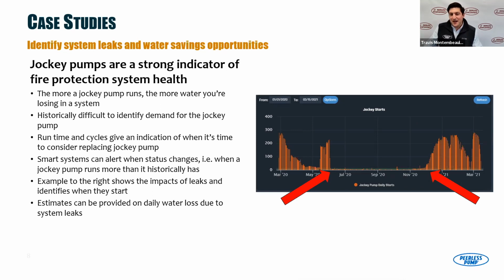So this site had 200, 300 starts per day. They tightened their system up in June of 2020, and they went down to 10, 15 starts per day. And then they had a leak that really happened around late November, early December. Starts went up again each day. And this is important. We talk about the sustainability piece. A lot of this information goes unknown.